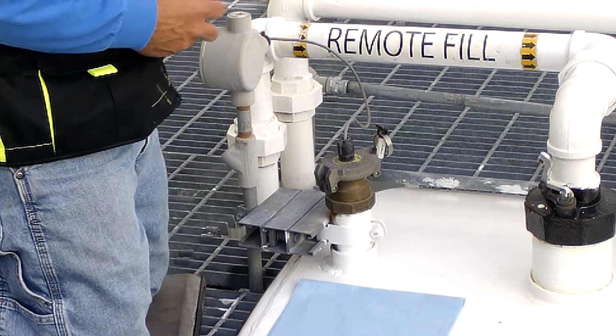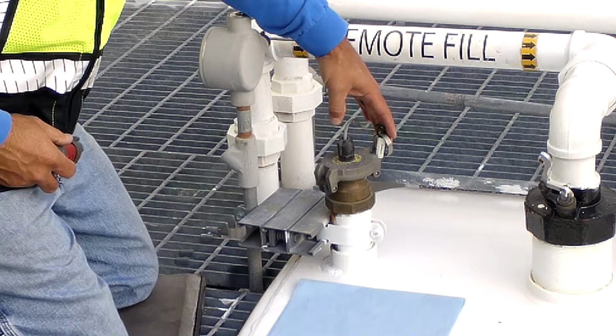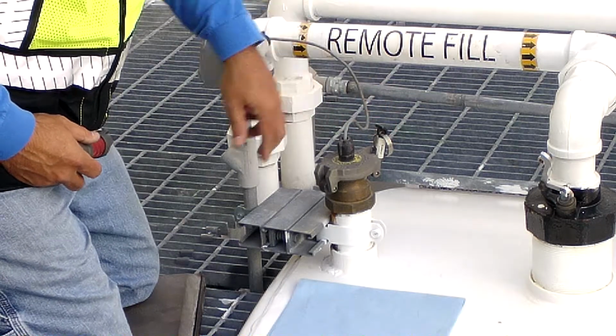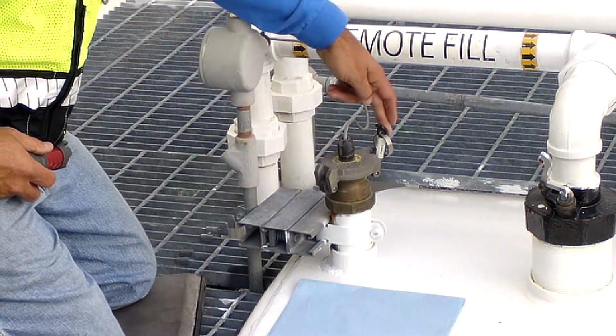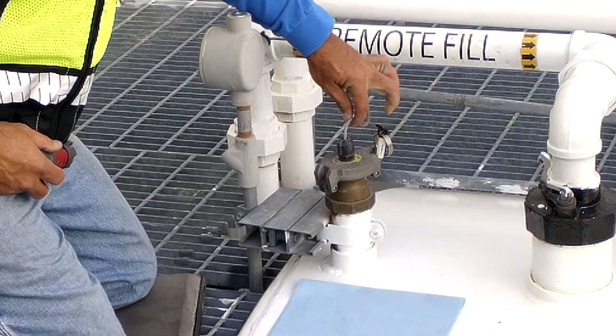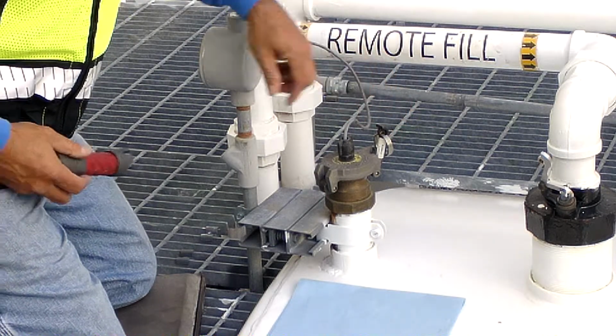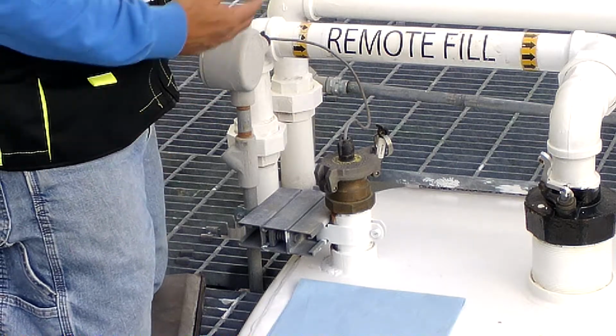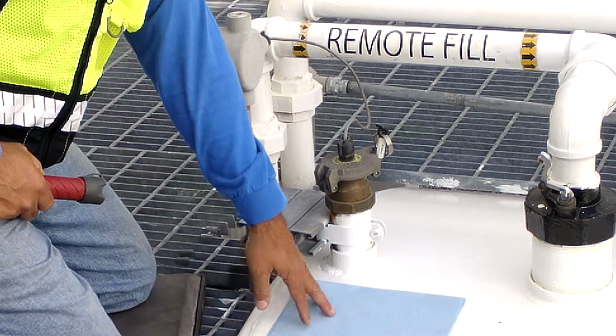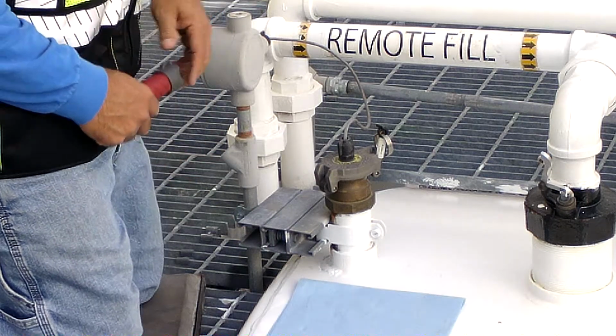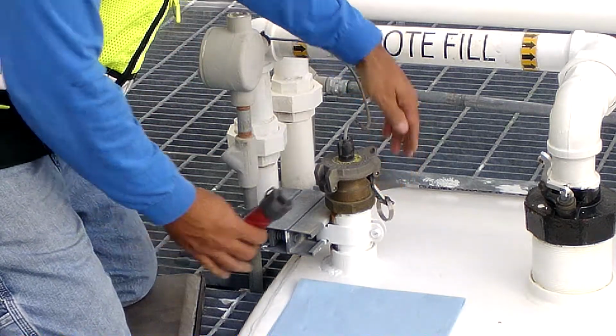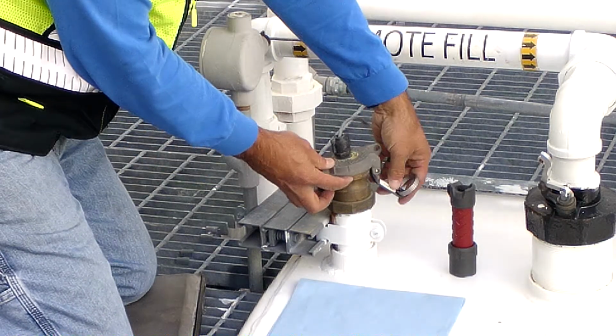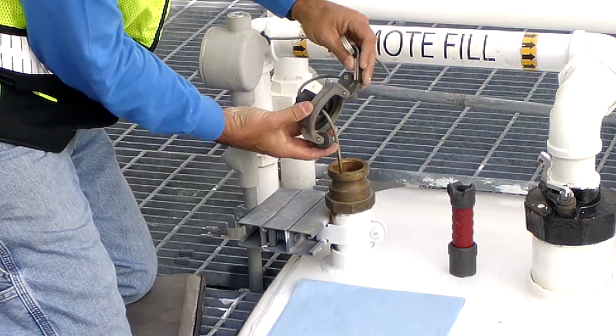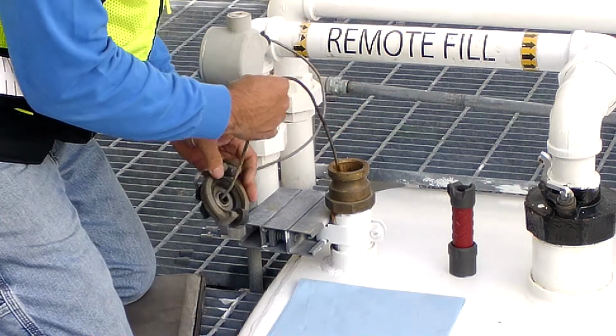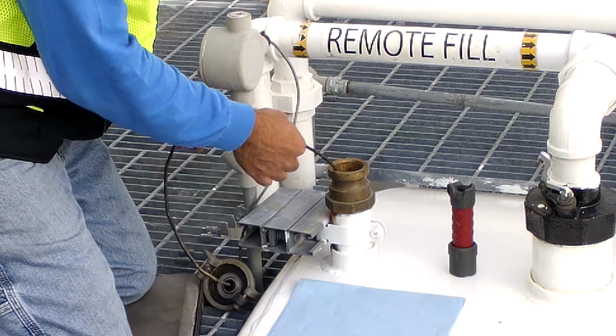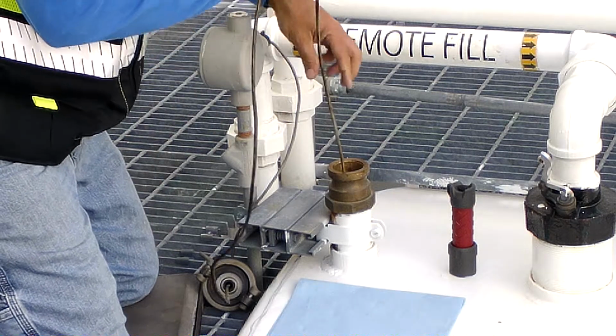Now that we've identified this tank's secondary riser being located here, we want to gain access to it by opening up this adapter to get to the sensor, which is identified through this cable. We have our flashlight so that we can look down into the riser, and then we have a shop rag in case there is any water. So first, this is a very easy access adapter, cam lock fitting. We open that. We now slowly begin to remove the cable.